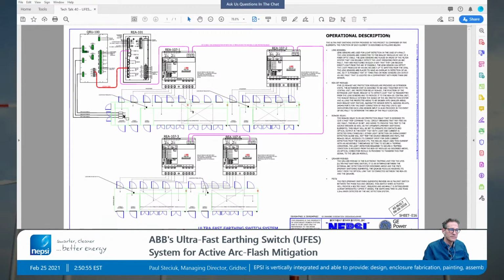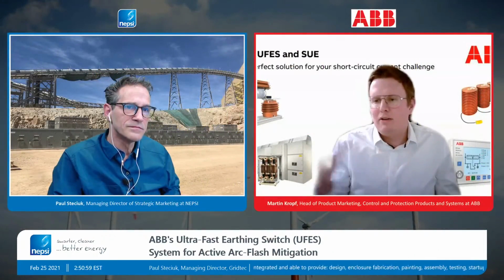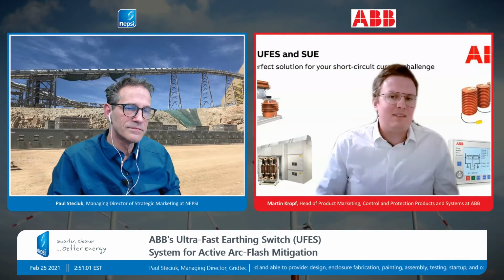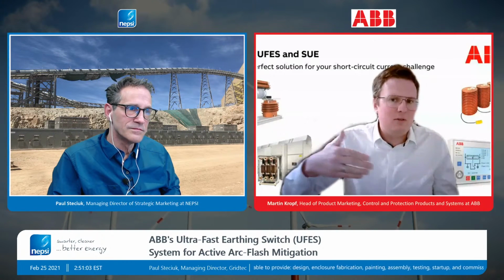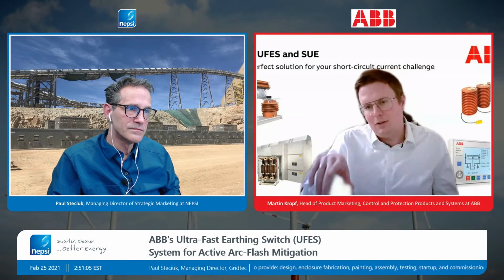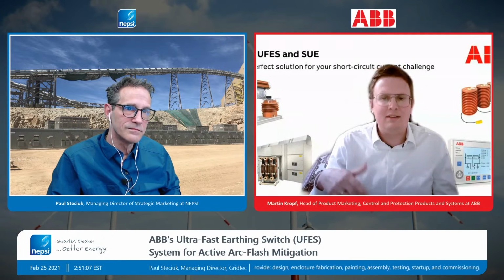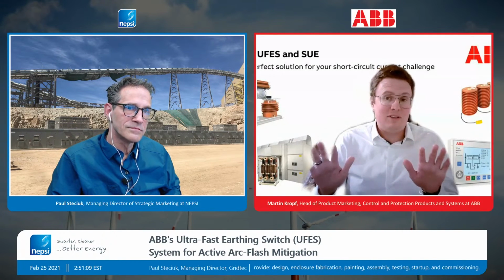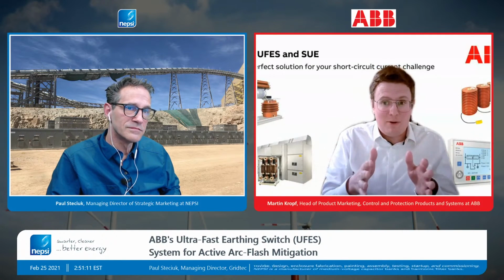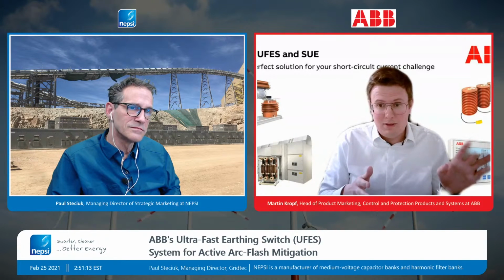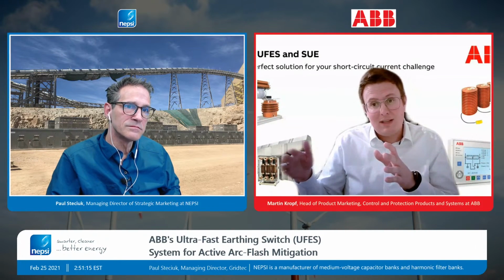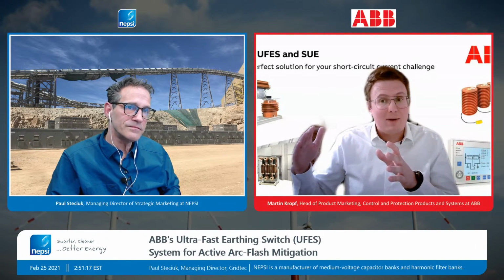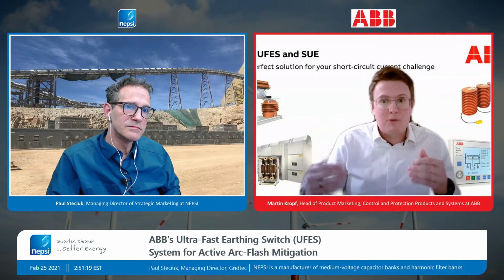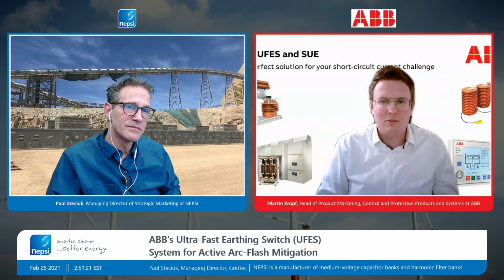This is really a great product as well, since we have a lot of options here. We can extend it as far as you really want. We can put the ring light sensor module in, and you can also make it selective. You can say, if it's happening in that area, I don't want UFES to trip, or in that area, I'd like just the tie breaker to open. So you have a lot of options, you can tune your system.